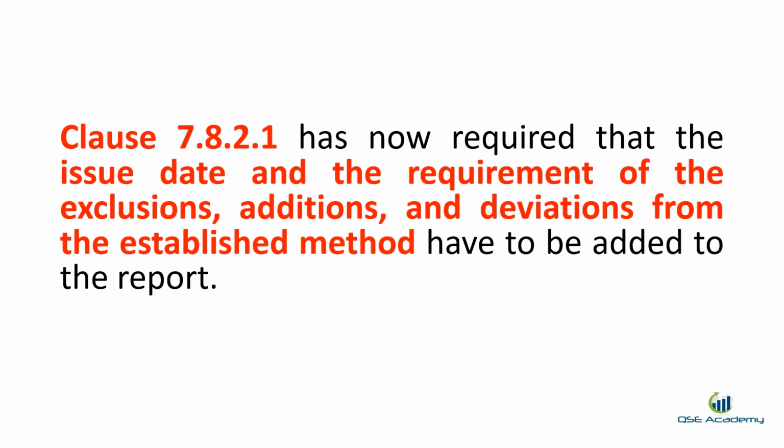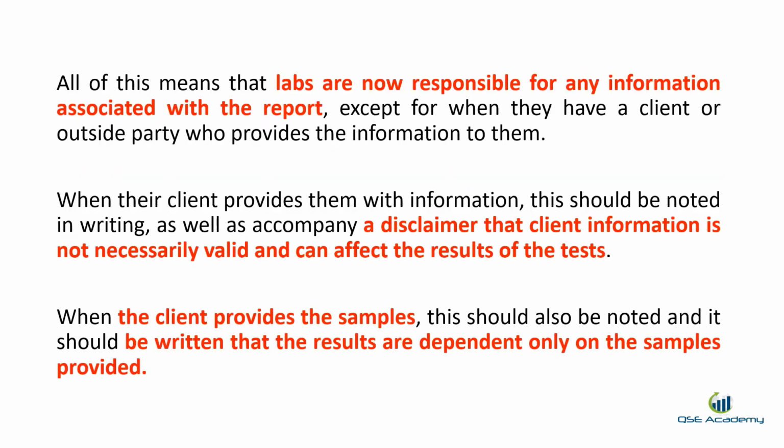Clause 7.8.2.1 now requires the issue date and the exclusions, additions, and deviations from the established method. All of this means that labs are now responsible for any information associated with the report, except for when they have a client or outside party who provides the information to them.